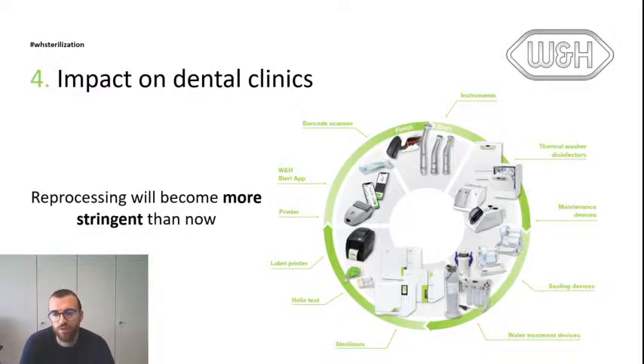So if we return to the workflow, after cleaning and lubrication, it's important to dry the instrument before packaging. Packaging is key to maintain sterility after the sterilization process. So it's really important to have good cleaning and after that a good sealing of the device.